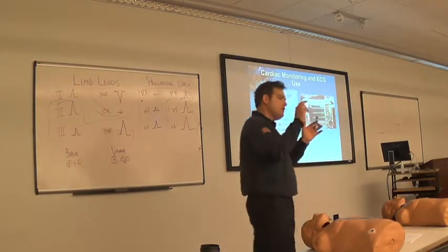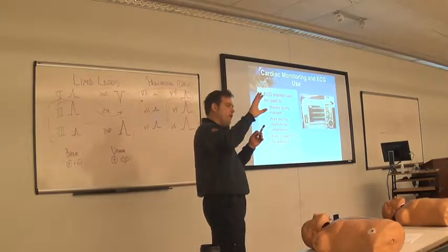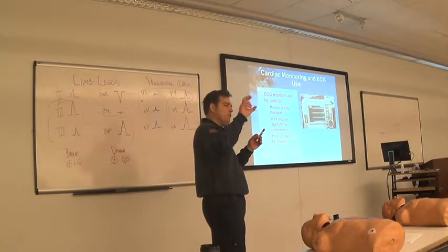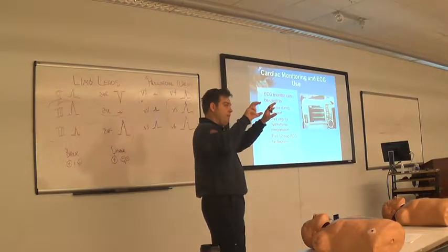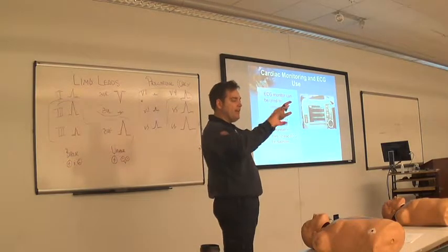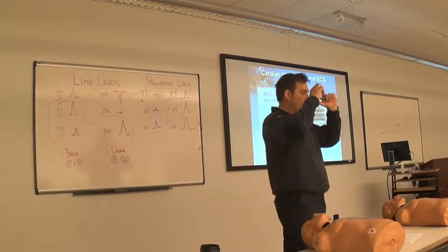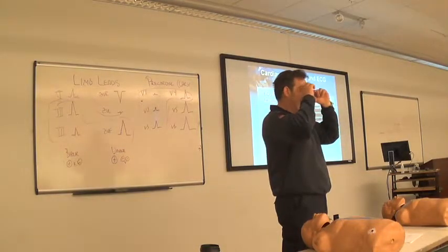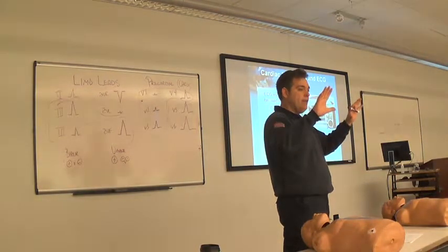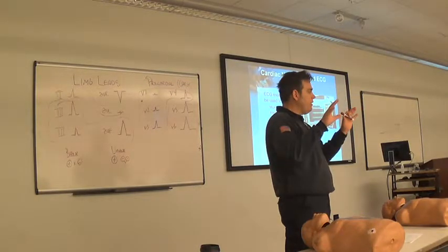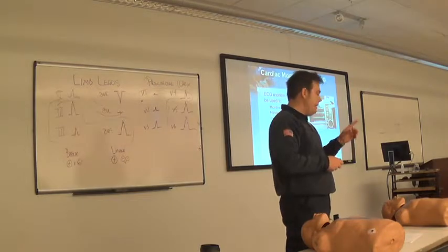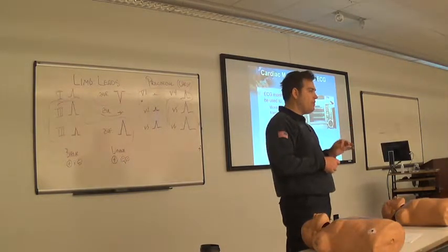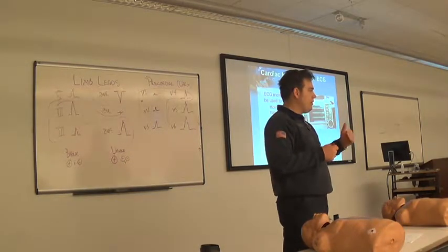Okay? Versus if we switch, when we acquire a 12 lead, the machine switches to what's called diagnostic mode. So we're in monitor mode, and then briefly it switches to diagnostic mode. That's putting the glasses on. And it's really refining what it is that we see. The downfall with monitoring diagnostic mode is you're going to get artifact all over the place. Any sudden movement, twitch, whatsoever, it's going to come across as artifact.